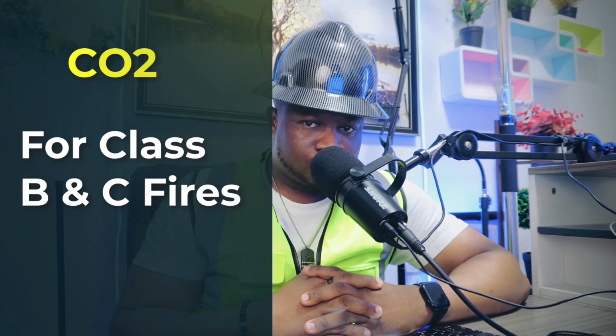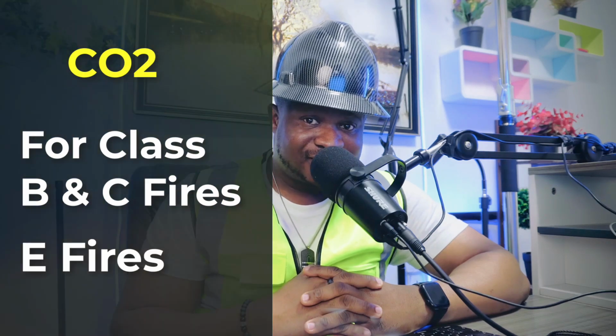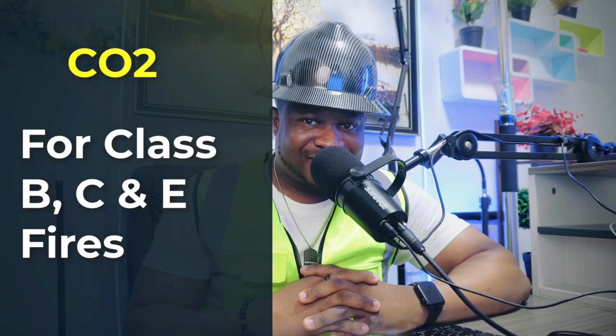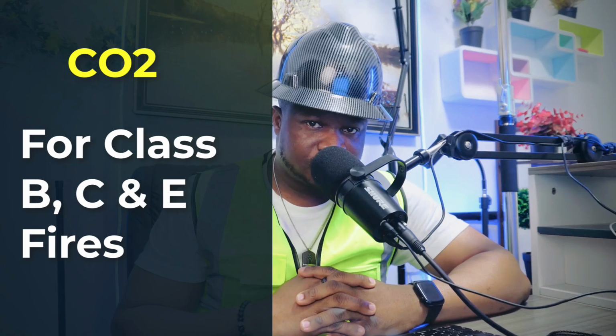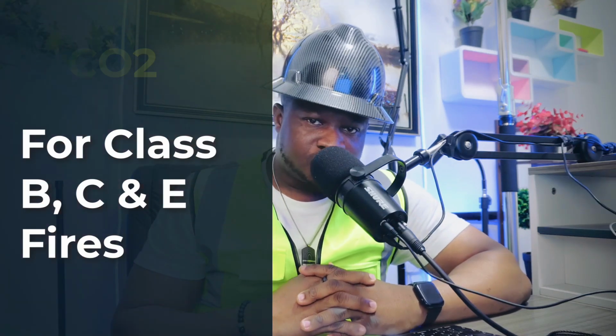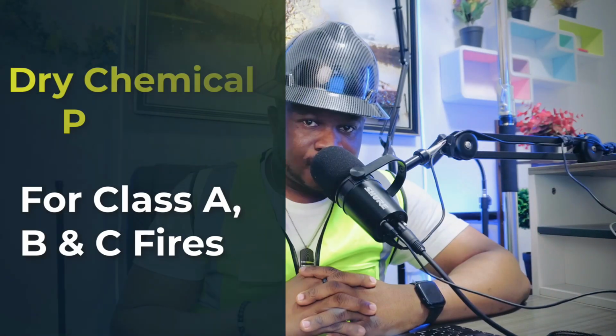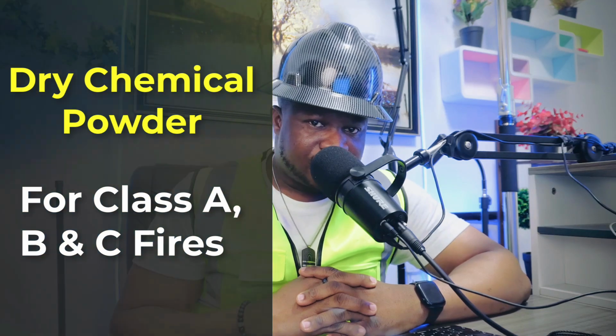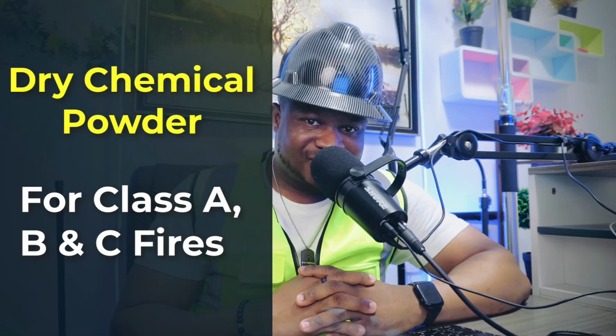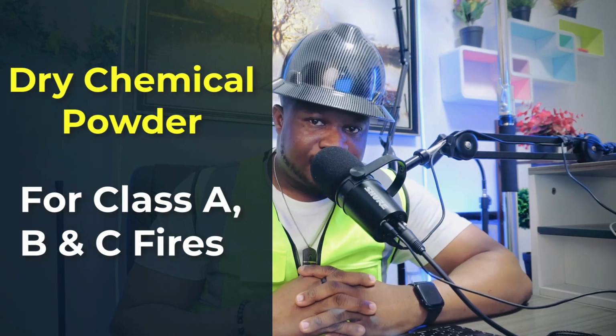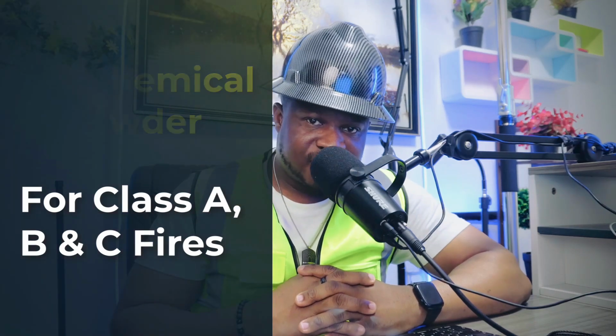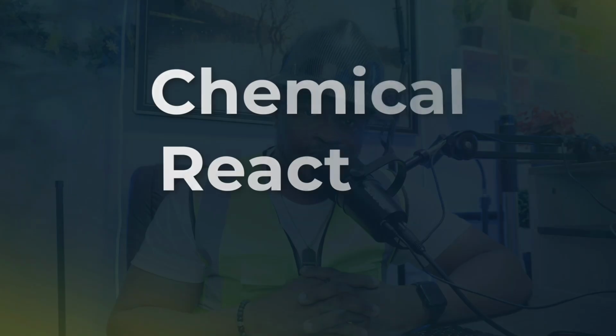Interestingly, CO2 is also suitable for Class E fires, that is electrical fires, due to the fact that it does not cause physical damage to electrical appliances. Dry chemical powder is used for Class A, B, and C fires. Dry chemical powder inhibits the chemical reaction which sustains the burning process, thereby stopping the growth of the fire to immediately extinguish it. This method of extinguishing is called chemical reaction inhibition.